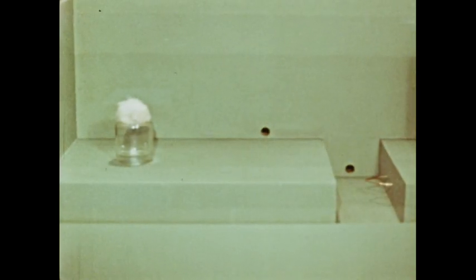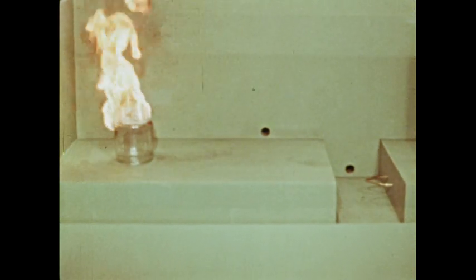These are the vapors given off from a piece of dry ice. Notice how they are heavier than air, settle to the floor, and collect in the pit. Low flash flammable liquids are continually giving off invisible vapors which act in exactly the same way. It is these vapors, not the liquid, that ignite and burn. Using a piece of waste saturated with gasoline, you cannot see the vapors, but they are settling to the floor and flowing into the pit just as the dry ice vapors did. When they reach the spark plug, fire immediately flashes back to the piece of waste. This shows why it is so dangerous to use flammable liquids exposed to the air — the unseen vapors are likely to reach a source of ignition and envelop you in a flash of flame.